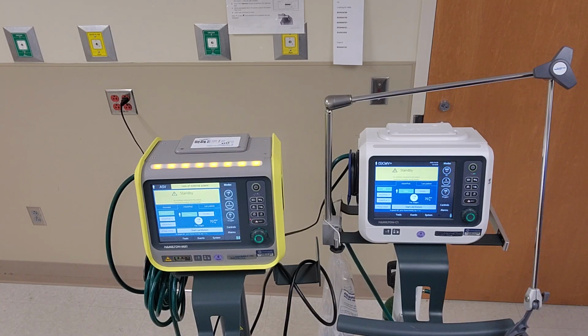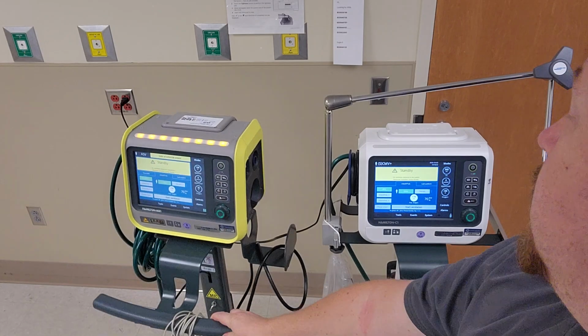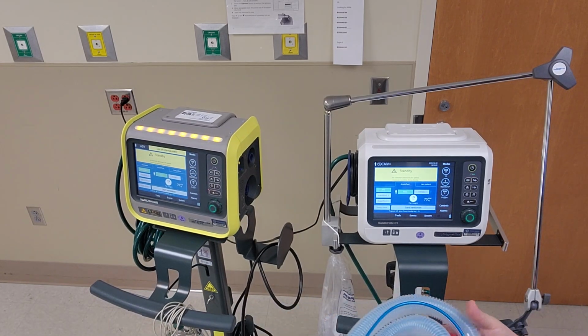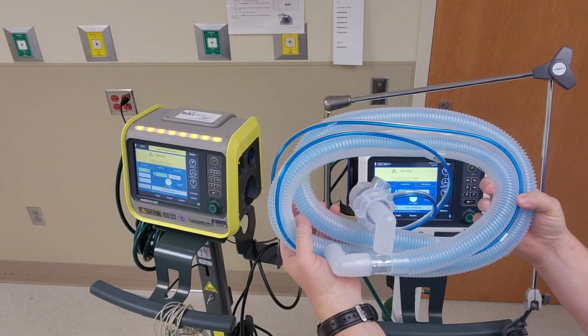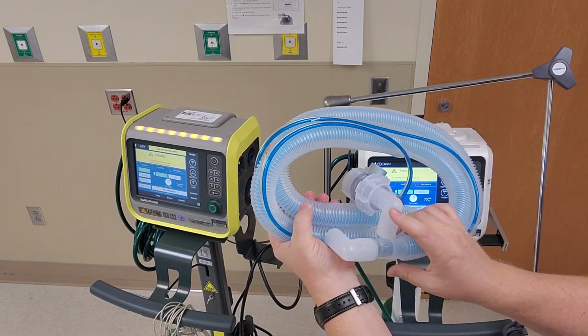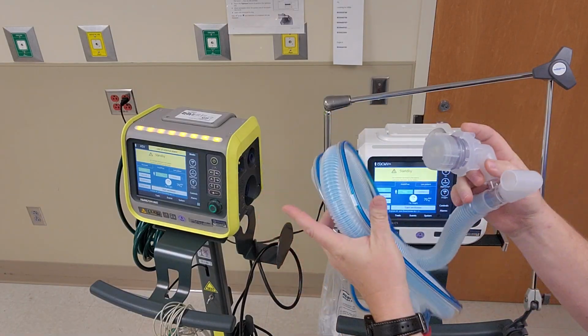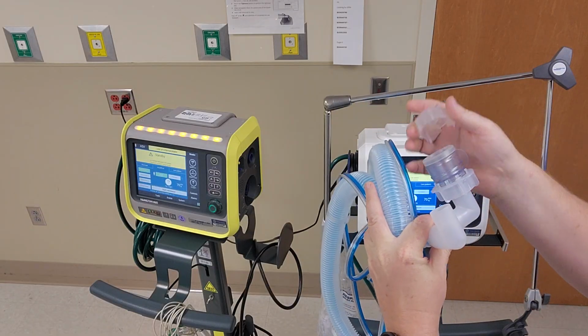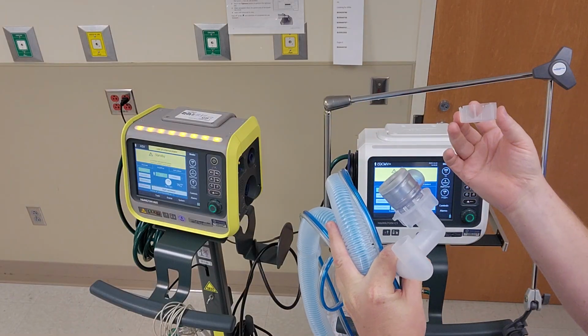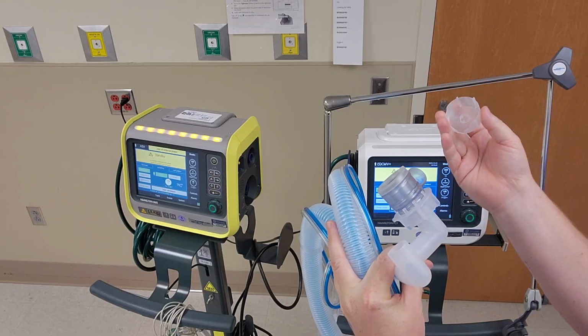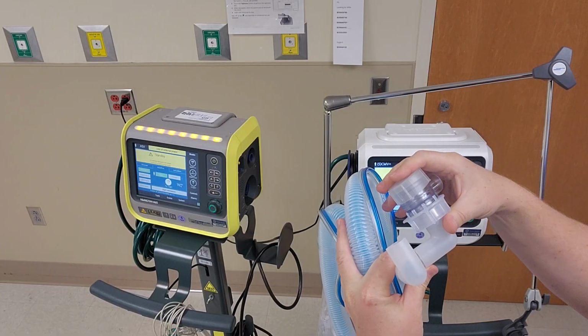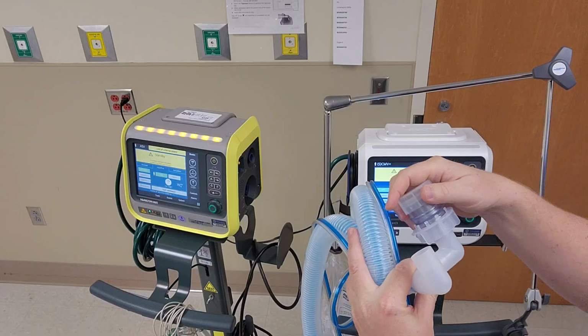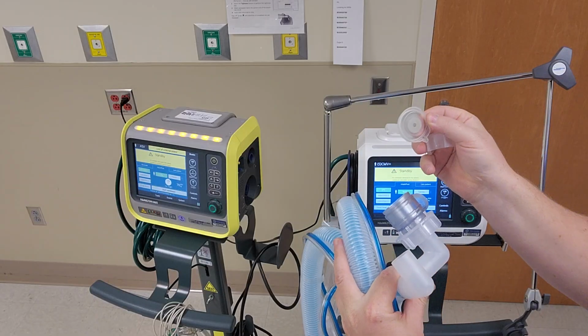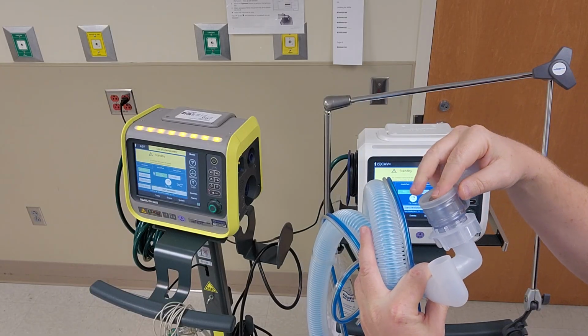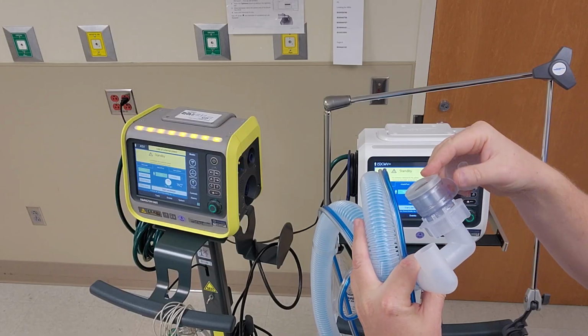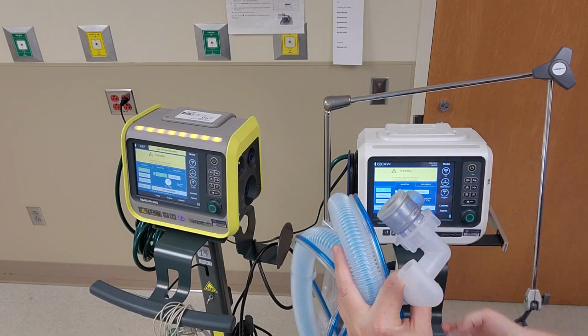So first off, when we're setting up the device, go with the C1 first. You're going to get that package, and it's going to be kind of coiled up like this. On this, you're going to have this exhalation valve. Make sure that you take off this plastic piece. Do not throw this away. The reason being is it's really nice to have this to actually cover this back up for when you are done with your trip. That way this little exhalation diaphragm here doesn't actually disappear and make your life miserable when you're trying to put it back together for the next trip.